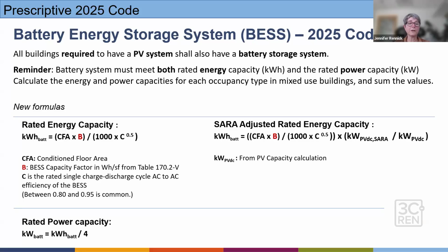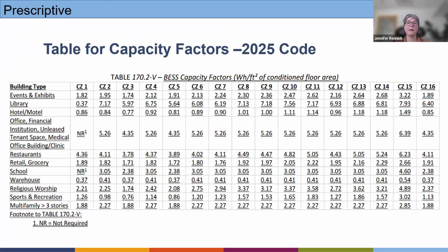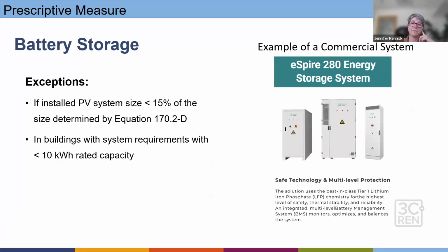There's a different table that goes with it. And so now you'll look at a rated energy capacity and a SARA adjusted rated energy capacity if you're doing the SARA method, and then a rated power capacity where the formula is much more simplified. And then we have a new set of tables for those new factors, again, laid out by climate zone and by the building occupancy types.